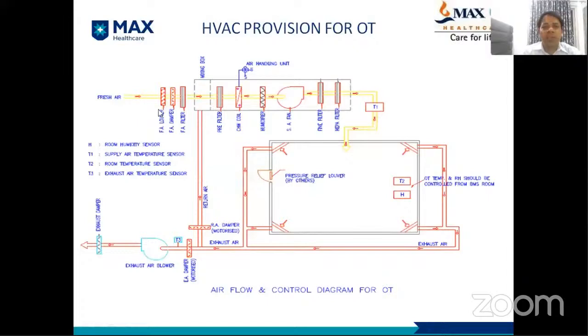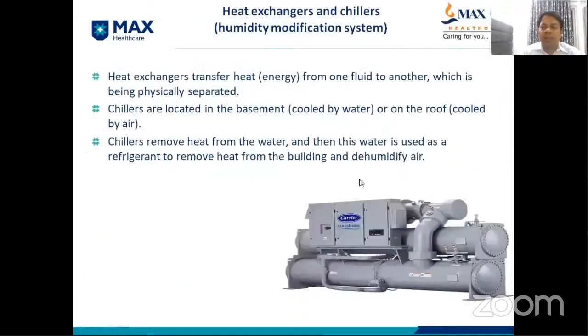It is almost similar: the fresh air goes through different stages, and finally this goes to the OT air conditioning, the OT room, with pressure relief louvers. Now coming to the heat exchangers and chillers. A heat exchanger transfers heat energy from one fluid to another, which are physically separated. Chillers are located in the basement, cooled by water, or on the roof, cooled by air.